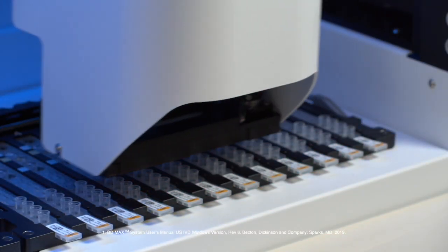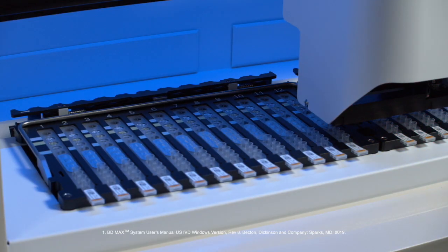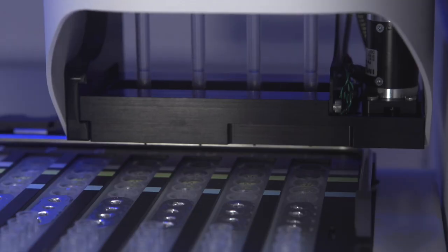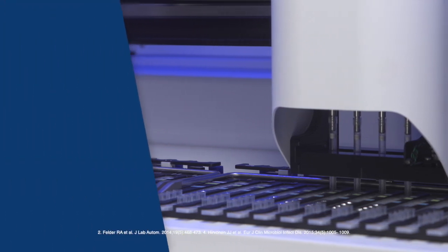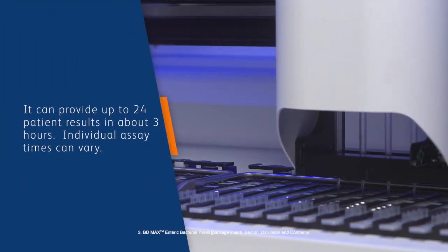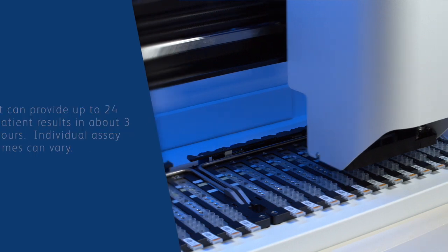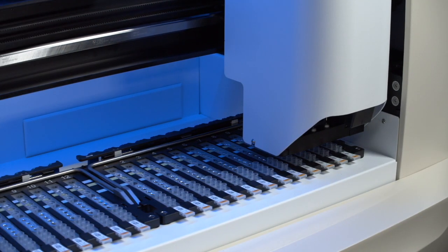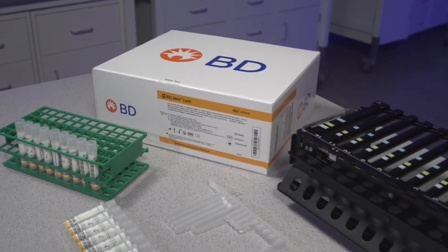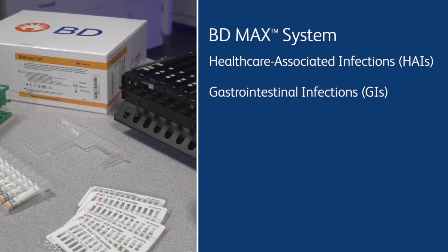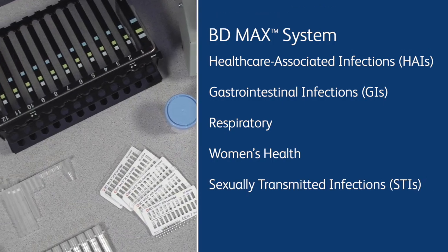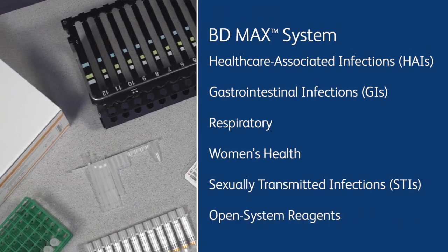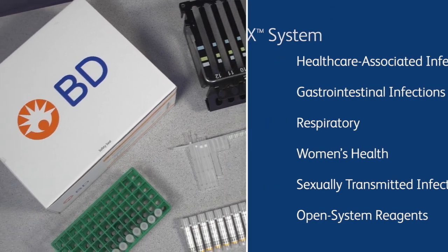The BD Max system for molecular diagnostics fully automates cell lysis, nucleic acid extraction, PCR setup, target amplification and detection from a variety of specimen types. It can provide up to 24 patient results in about 3 hours. Individual assay times can vary. The BD Max system can process a broad menu of IVD assays, including HAIs, GI, respiratory, women's health and cancer, and sexually transmitted diseases. The BD Max system can also handle open system assays for lab-developed tests.